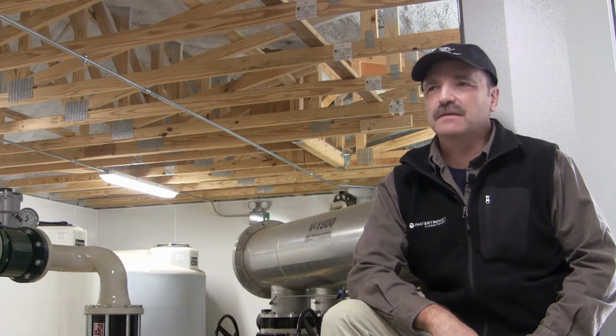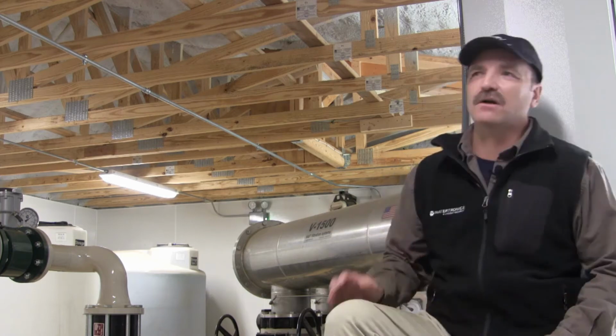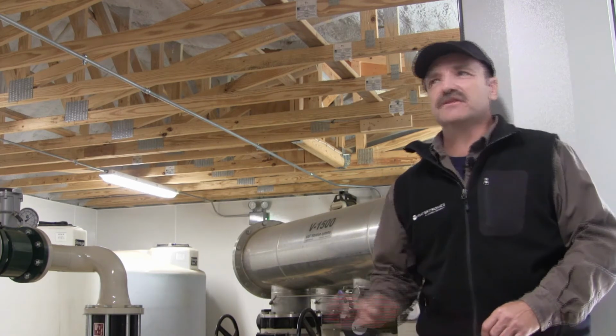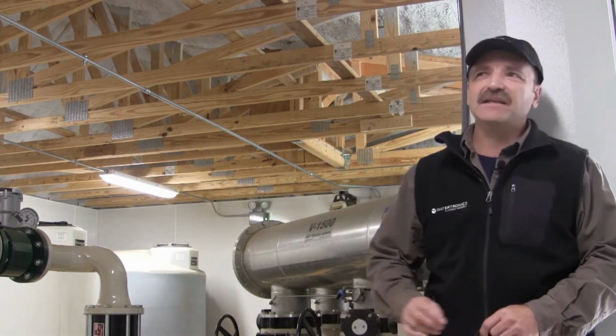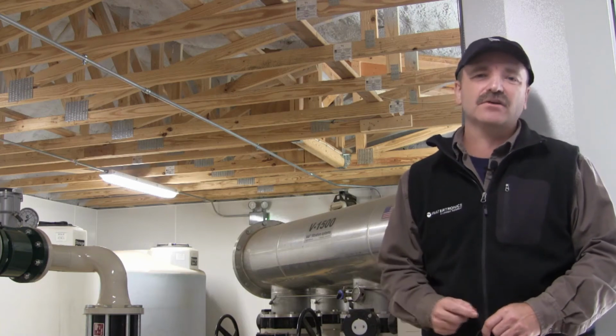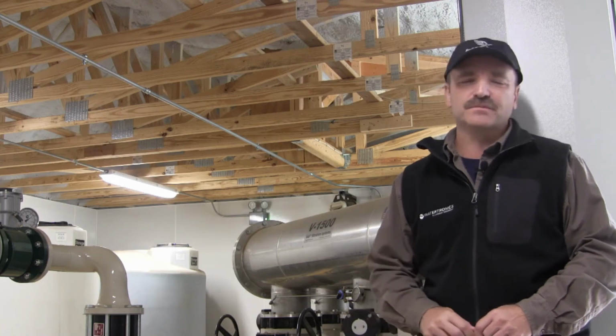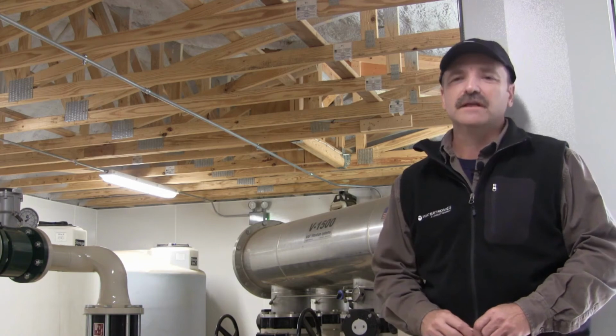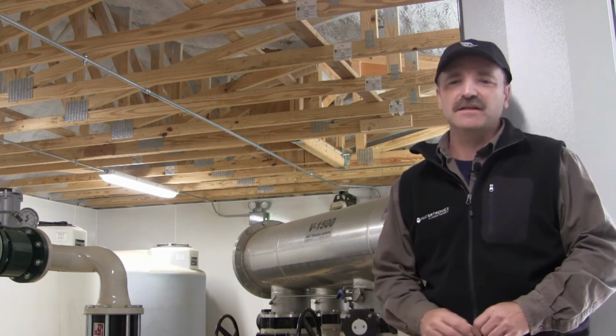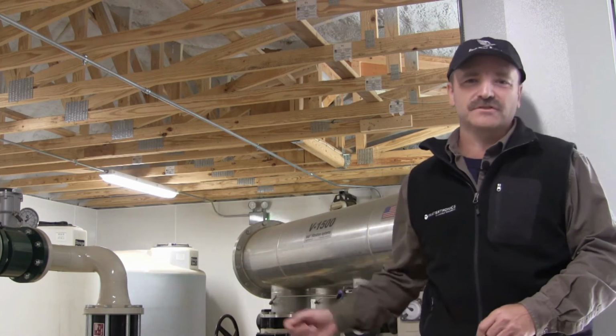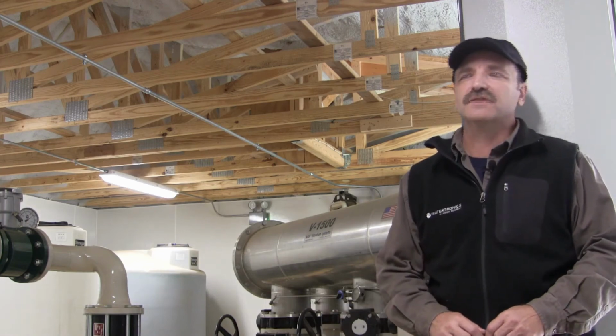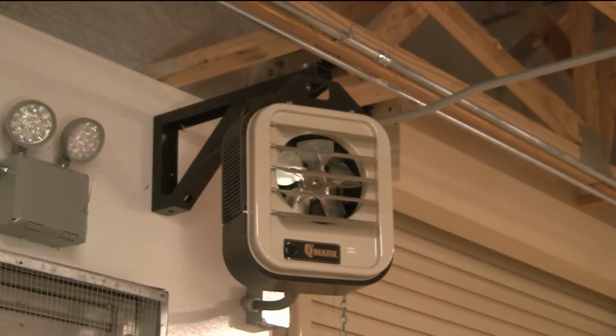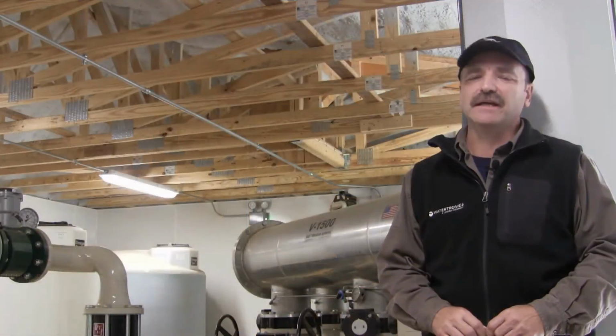So one of the biggest problems we come across every fall and into winter is there isn't enough heat in the pump station. I can't tell you the number of pump stations that I go into and they've got a space heater plugged into the wall, and it may be putting out heat for about 2 feet, but the equipment is 20 feet away. So it's worth taking the investment in a quality heater in such a way that you know it's always going to be warm and you don't have any issues.